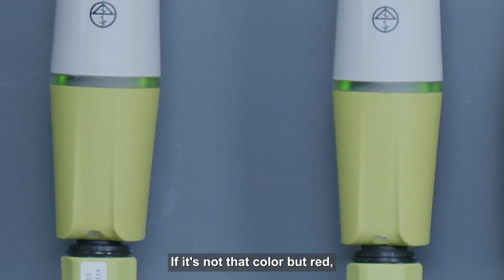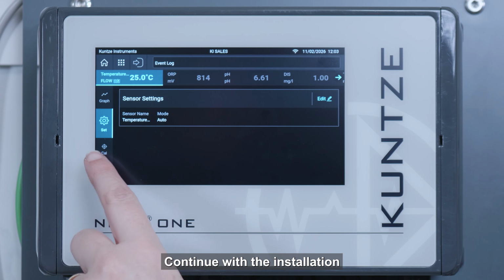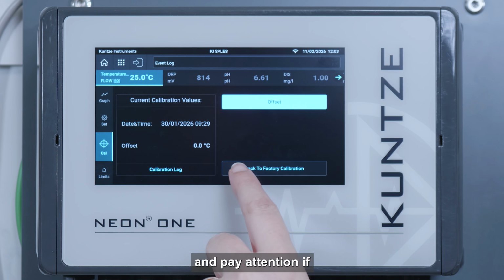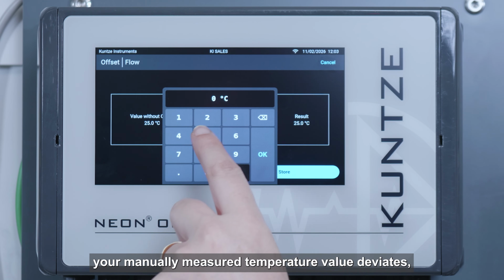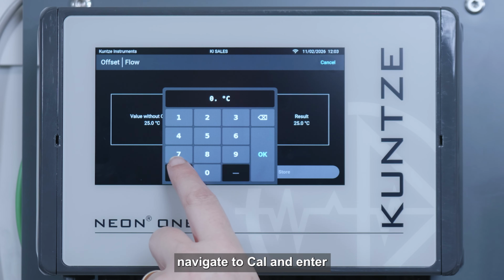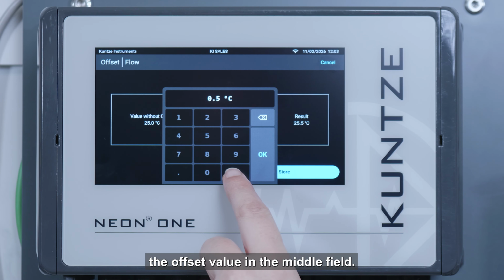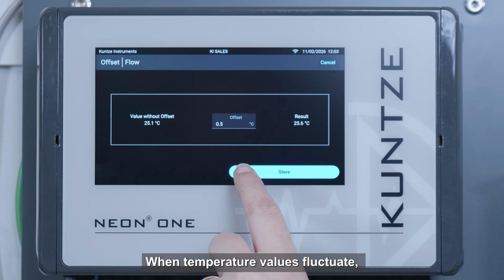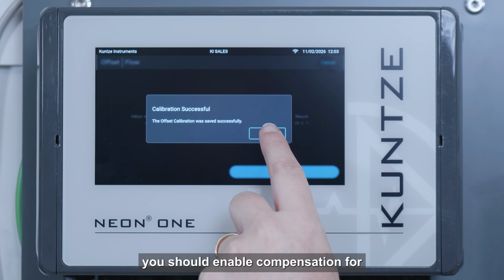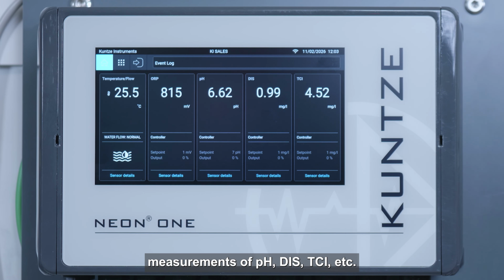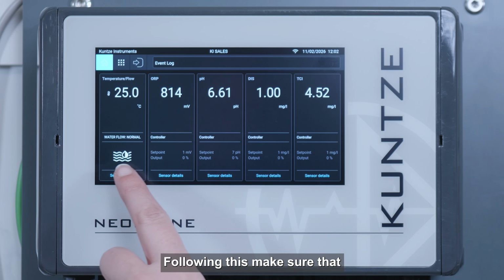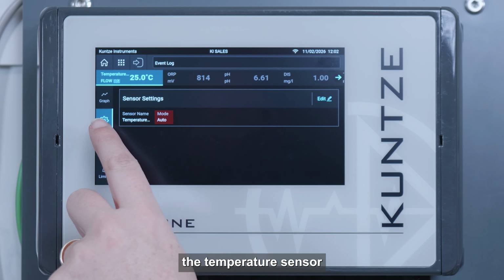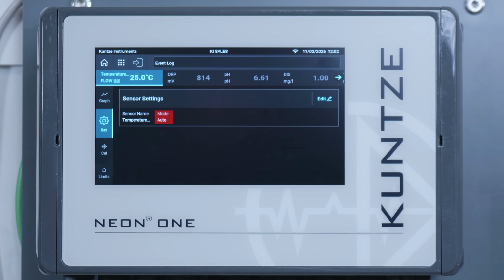If it's not that color but red, the sensor is not defined. In that case, define the sensor group, continue with the installation, and pay attention if your manually measured temperature value deviates. Navigate to Cal and enter the offset value in the middle field. When temperature values fluctuate, you should enable compensation for measurements of pH, DIS, TCL, etc. Following this, make sure that the temperature sensor is in auto mode.